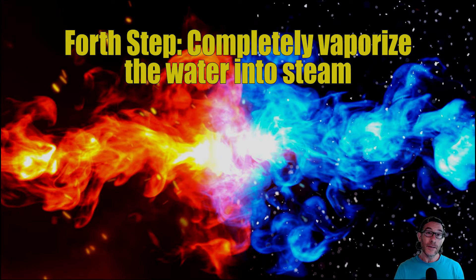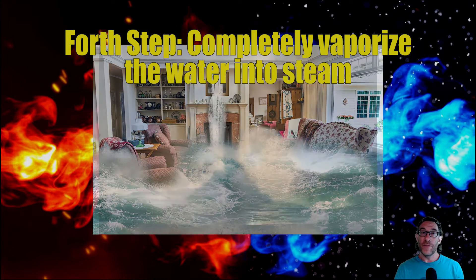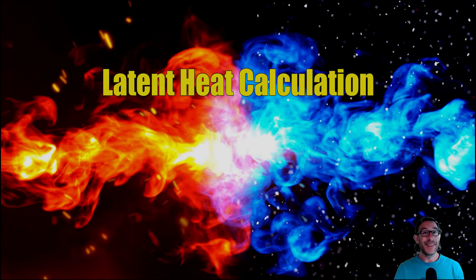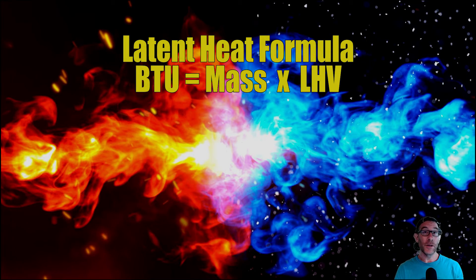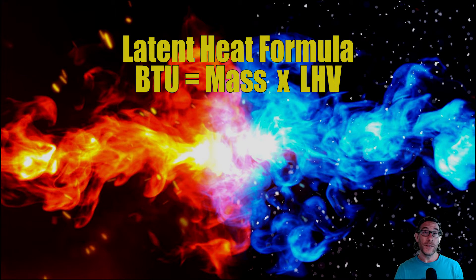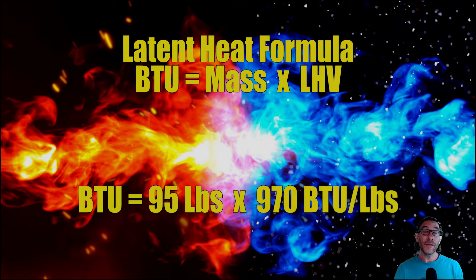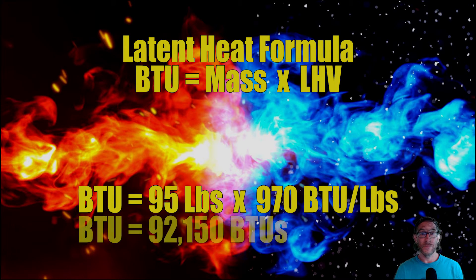Fourth step: let's take this 95 pounds of water and vaporize it into steam. This is a latent heat calculation. The latent heat of vaporization is 970 BTUs per pound. Plugging into the formula — BTUs equals mass times latent heat of vaporization, or 95 pounds times 970 BTUs per pound — to change 95 pounds of water into steam will consume 92,150 BTUs. We're going to write that down for the very end.